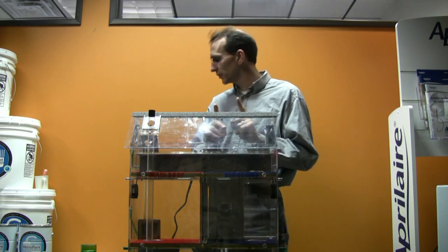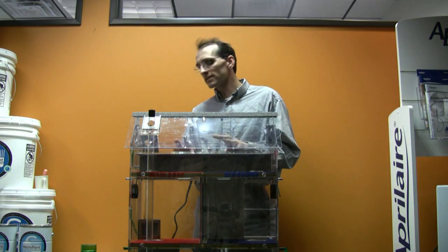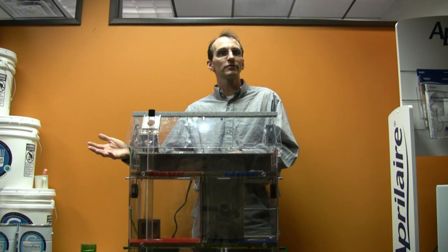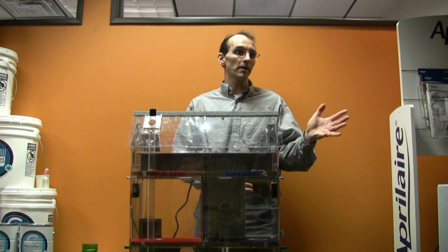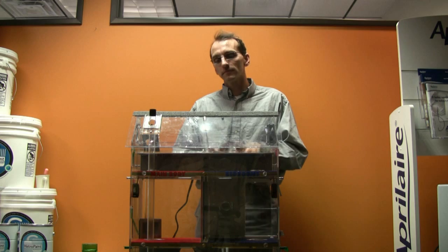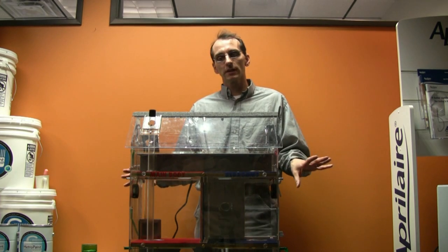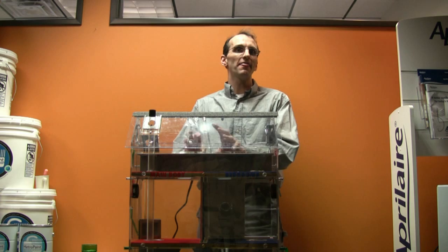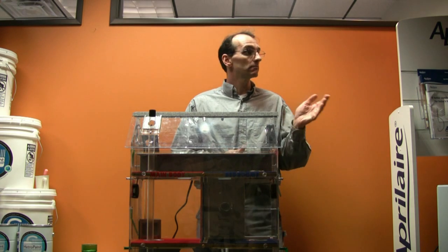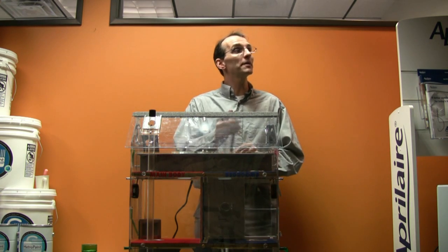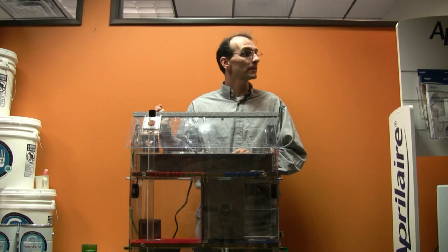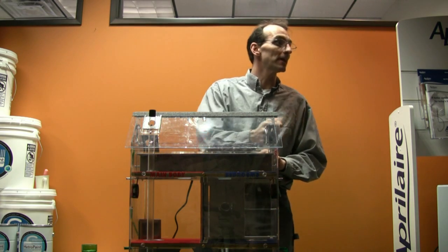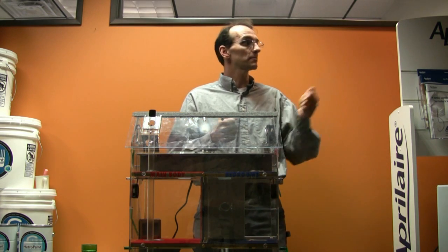So the other thing I wanted to show you was how these fan effects could pressurize one part of the house differently than another part of the house. So this was the basics around how to do combustion safety testing. You try to find what is the worst condition you could put that part of the house in. And to your point earlier, sometimes that might mean you leave this door open. Sometimes it means you leave the door closed. Sometimes it means you leave that fan on, and sometimes you don't.